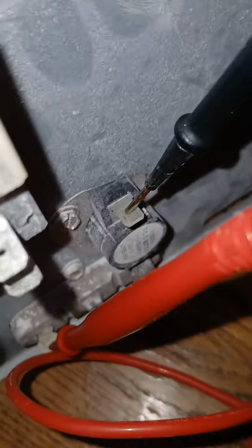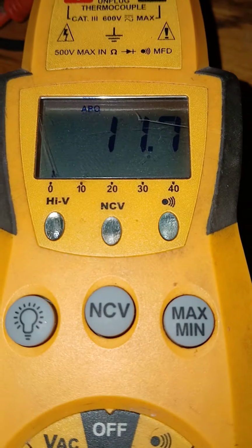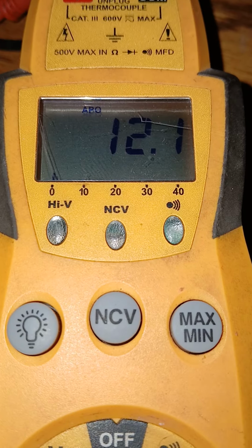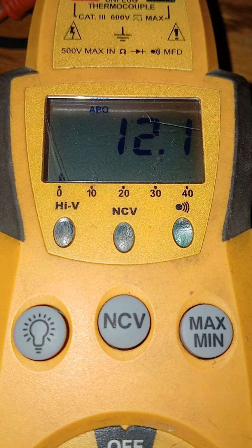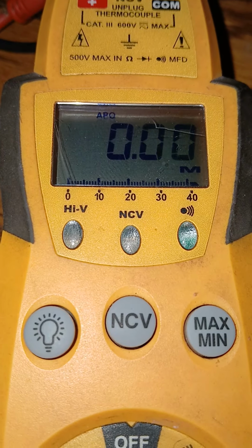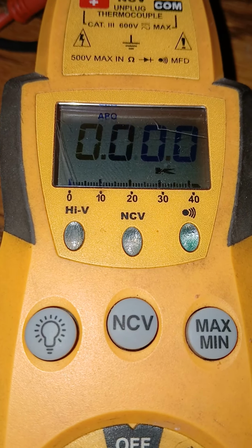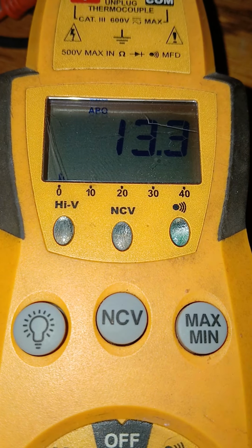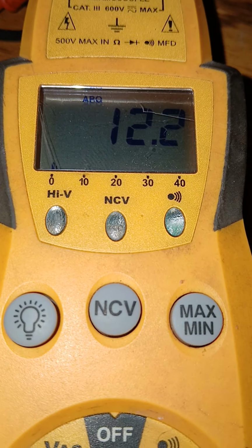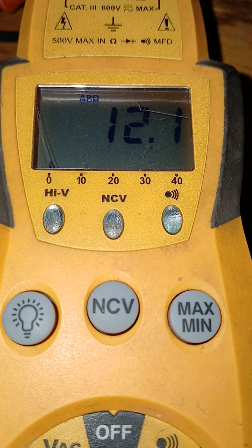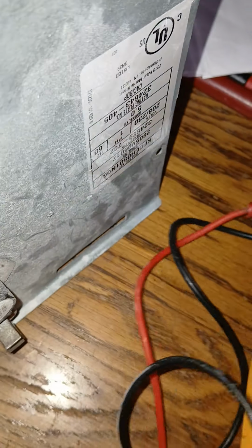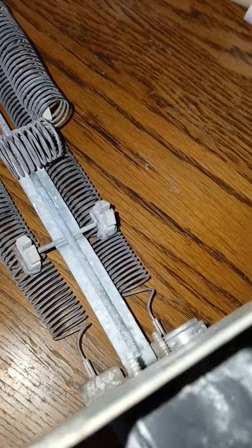Now we've got this lead here. We go over here, and I put this on here. Once I do, we're reading, well, that one pops up to 12.1, but it's in the 11.5 to 12 range, somewhere thereabout. Touch it again, and we get somewhere thereabouts. It depends on how good the connection, 11 point something to 12. So I'm under the impression that these heat strips may be good. If they were bad, they may read OL. So that's just a quick way to ohm out the heat strips to see if they have resistance.